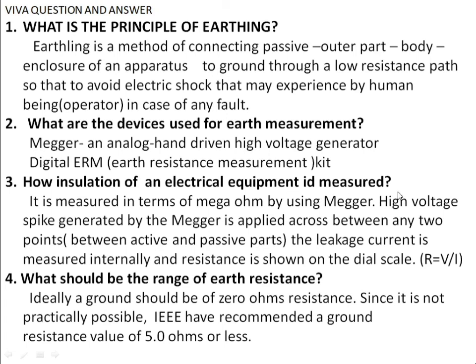What should be the range of earth resistance? Ideally, ground should have 0 ohm resistance. Since it is not practically possible, IEEE has recommended a ground resistance value of 5 ohm or less. So as per the IEEE standard, the ground resistance should be less than 5 ohm. I hope you are all able to understand the experiment, what we discussed so far.